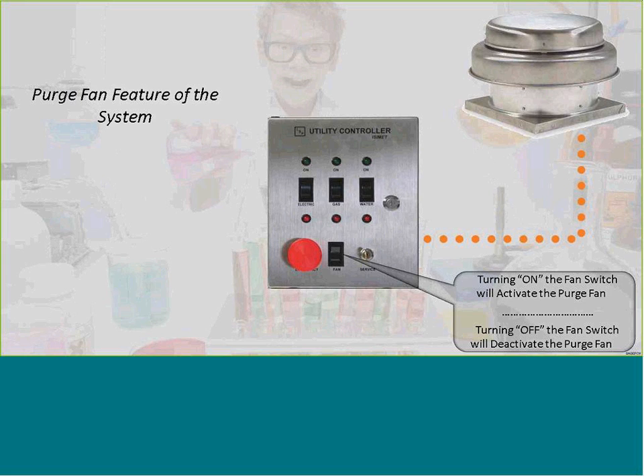This is just showing how you turn the switch on and off. And this is an alarm input to deactivate the fan. As we spoke before, we do not want the fan to run if there's a fire inside the building, because we know that more oxygen fuels the fire. So an alarm signal coming in will not let the purge fan come on. It only comes on in a panic situation, not an alarm.